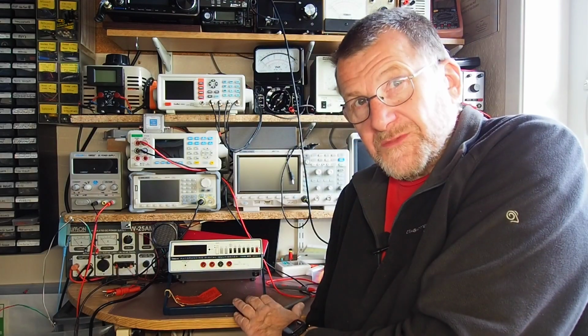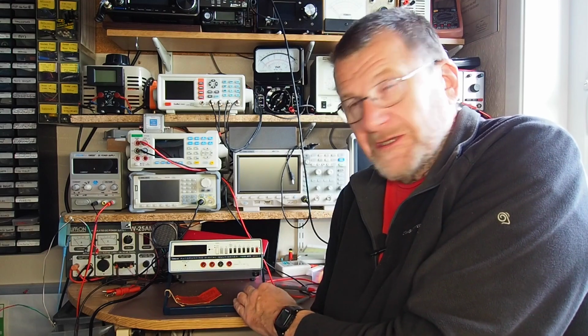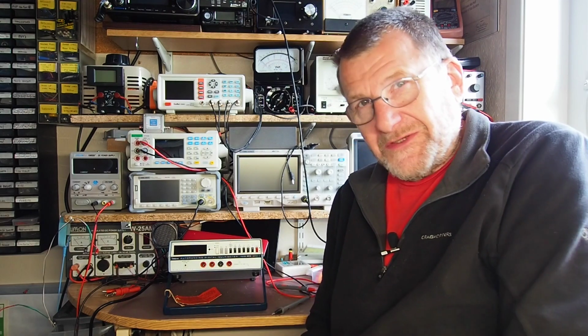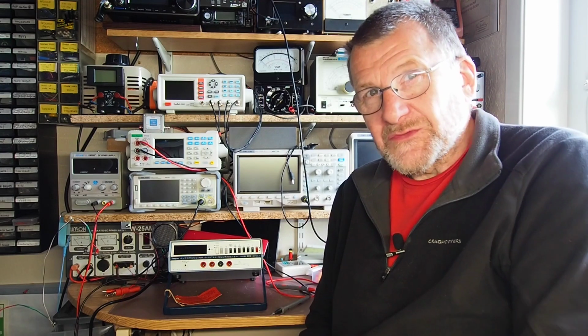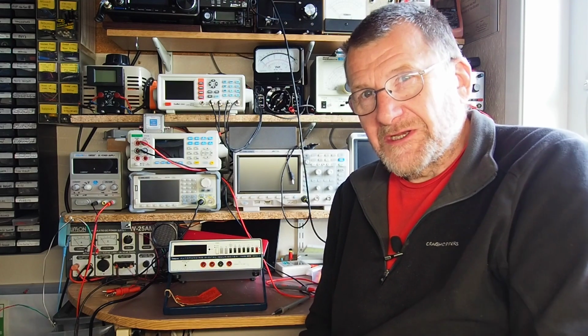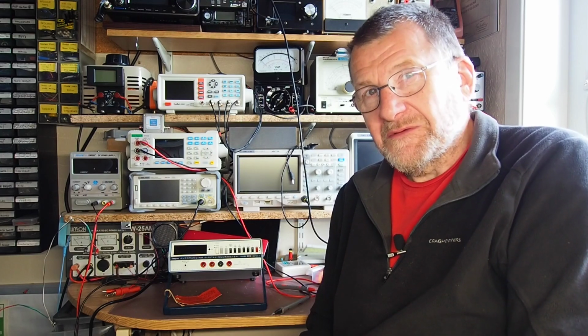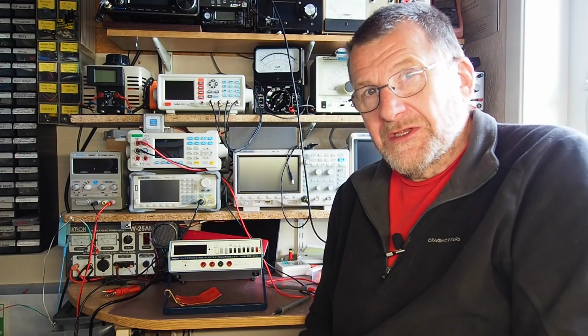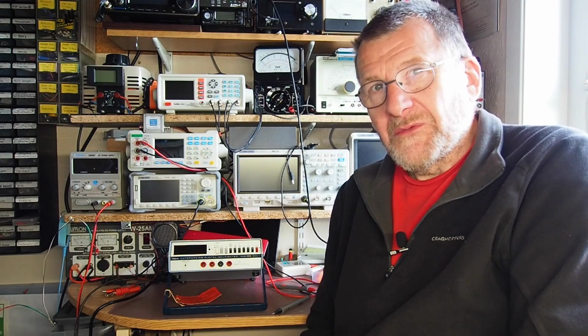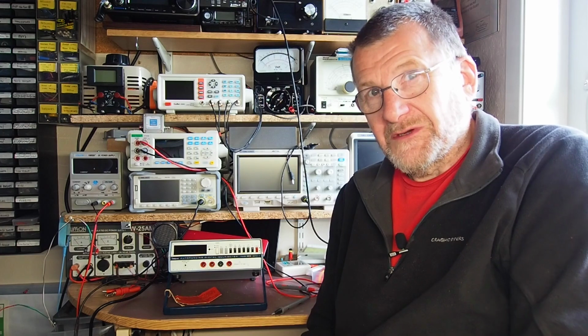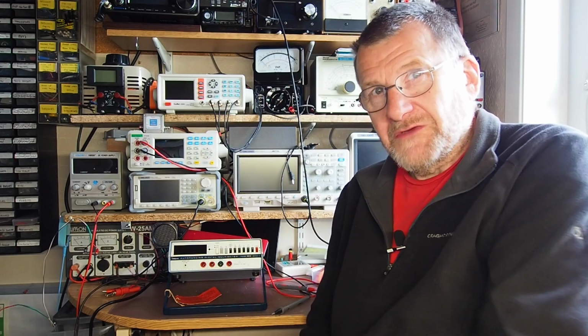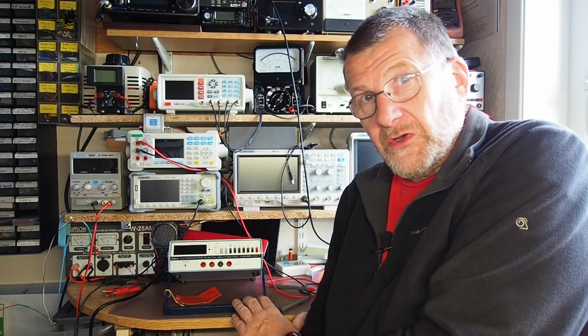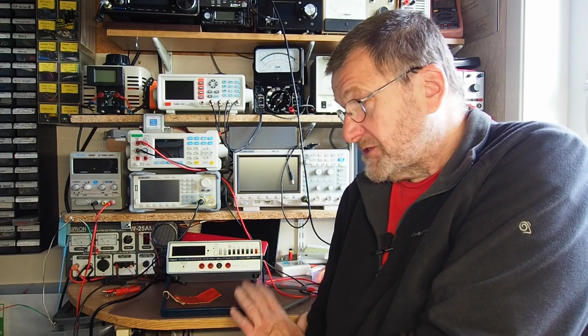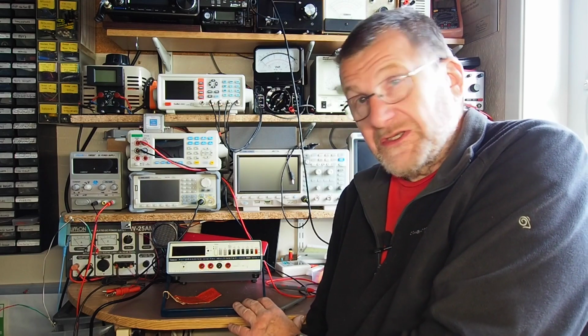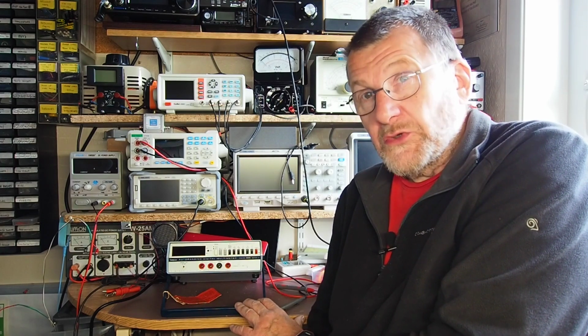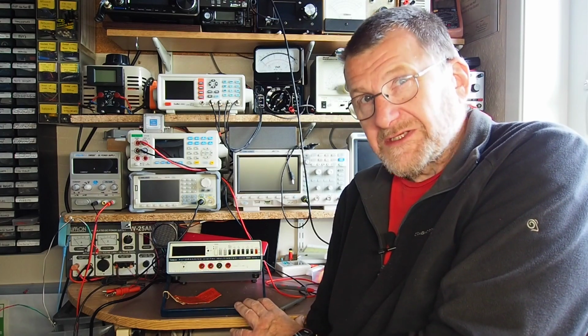Okay, well that's the Simpson 465 meter, seemingly brought back from the dead. I took a chance with my £13.48 on eBay, and it's worked out for the best. So well done, Simpson, for fitting a fuse that did its job. Somebody clearly thought about that carefully in the design, and it helped. So I'm pleased the transformer survived. I'm even more pleased that the transformer they fitted also has taps suitable for 240 volts. So that's the instrument now working on UK mains voltage, which is great. I was after a second bench meter, so that'll fit the bill nicely. It's probably good enough as it is for what I tend to use it for.